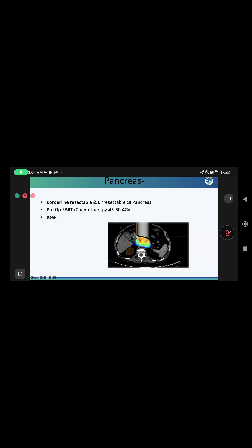If I give an example, the R90, that is the 90% range, is at 1.7 centimeter, whereas R50, that is the 50% isodose line, will be at a depth of about 2.2 centimeter, and when we go to 2.9 centimeter, there is almost zero dose. Such is the drastic dose fall off we see in electrons, which allows better sparing of the OARs and escalating the dose to the tumor bed.